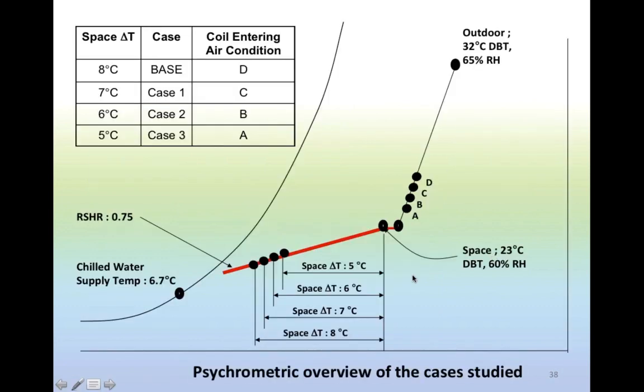So now, if you look at the psychrometric chart here, it's a busy chart, but basically the different conditions I'm looking at: there's a base case, a conventional 8-degree delta T, which is condition D at the entering point of the cooling coil, and then I go down to these other 3 points, A, B, and C. So C is 7-degree delta T, and then a reduced delta T of 6 degrees and 5 degrees. It's quite obvious, all else being the same for the same cooling load, when you reduce the delta T, the airflow increases. It's as simple as that. So what is the implication?